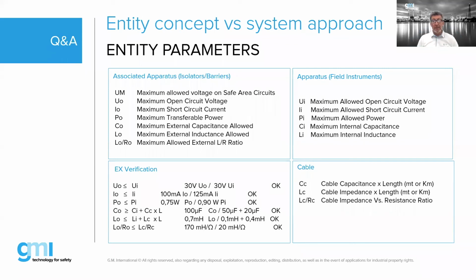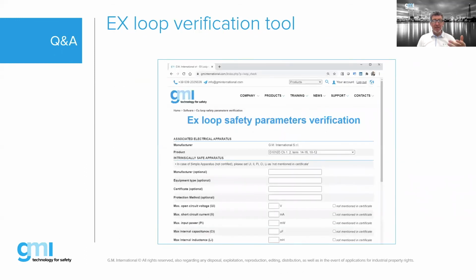No, not at all. And, you know, you make it sound very difficult. We need to check all these parameters, Uo, Ui, Po, Co, the cable parameters. But in reality, at least through GMI, and I'm sure there are other means around the world, we provide a safety loop verification tool online. You can download it online, you can work online, where the most difficult part is to collect the data, to have the information, to know what is the cable impedance and the cable resistance and capacitance. Once you have that, you can insert it into the tool, and then the tool will do the work for you. Yep. All right, let's go to next.